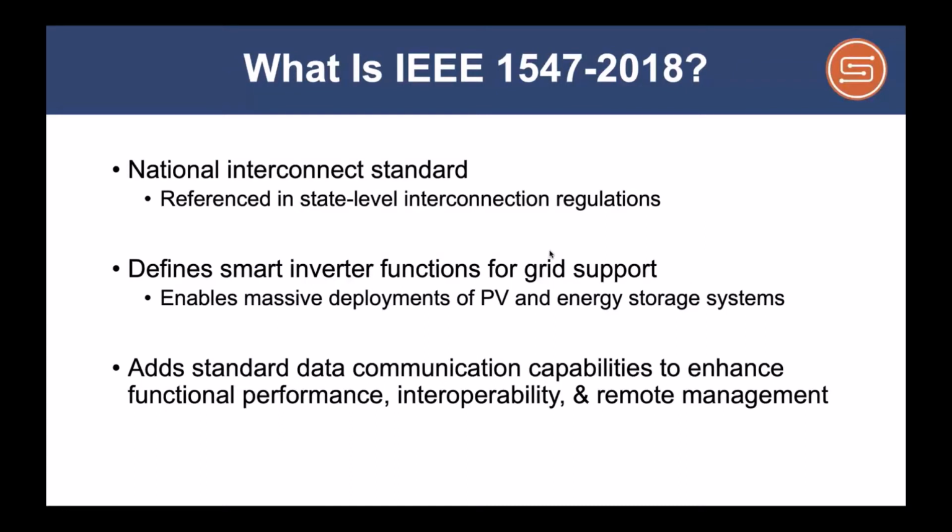Okay, so that's SunSpec Modbus, and I said it's part of 1547, but what's 1547 itself? It is the National Interconnection Standard specified by the Energy Policy Act of 2005. Interestingly, given the way our governing system works here, any national laws need to be referenced in local and state level laws, and IEEE 1547 is no exception. The interconnection regulations of all the different states will ultimately reference this standard. We'll see a map of this in a screen coming up.